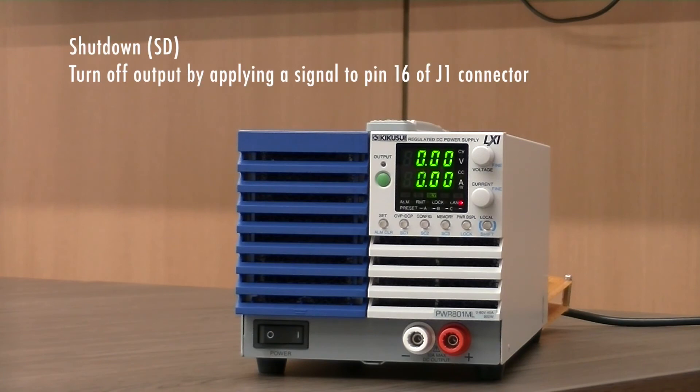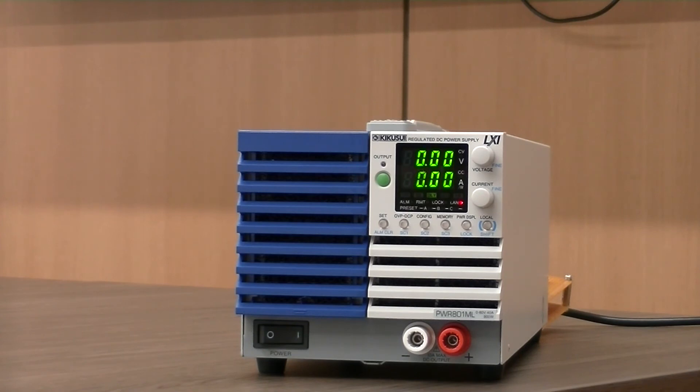The SD or shutdown function allows you to turn off the output by applying a signal to pin 16 of the J1 connector whenever an abnormal condition occurs. You can release the shutdown function by turning the power switch off and then back on.